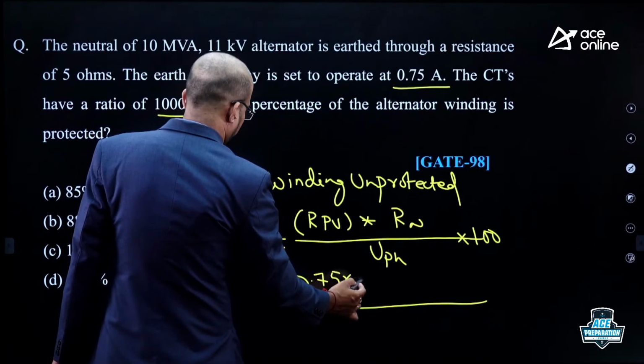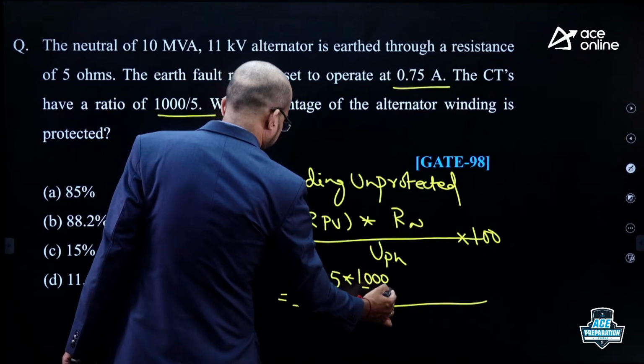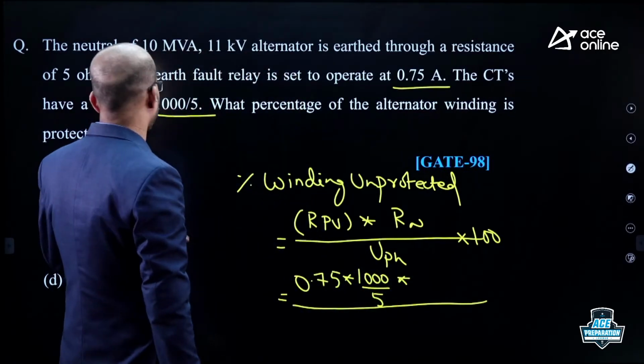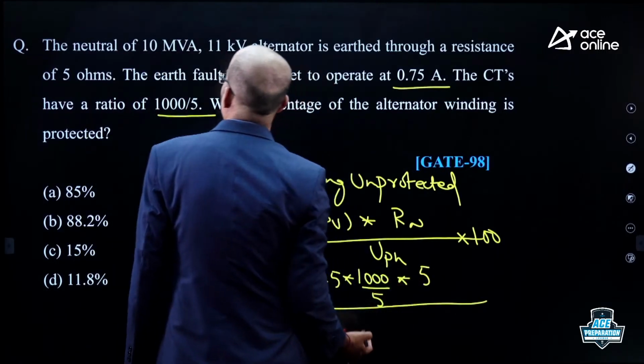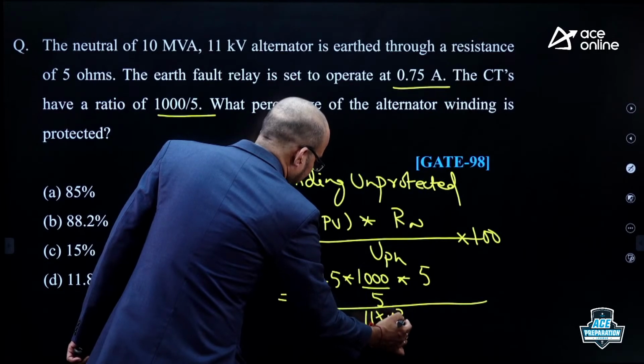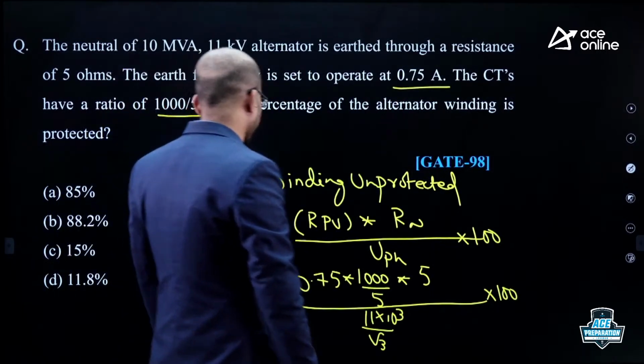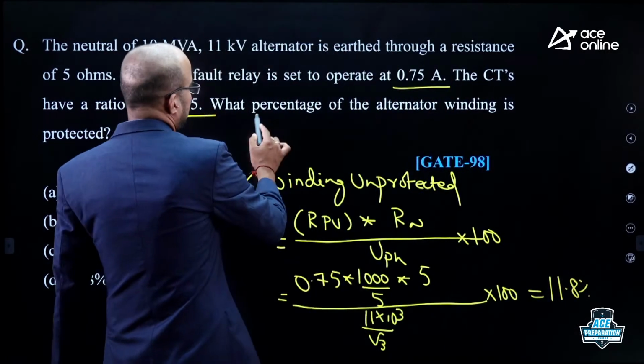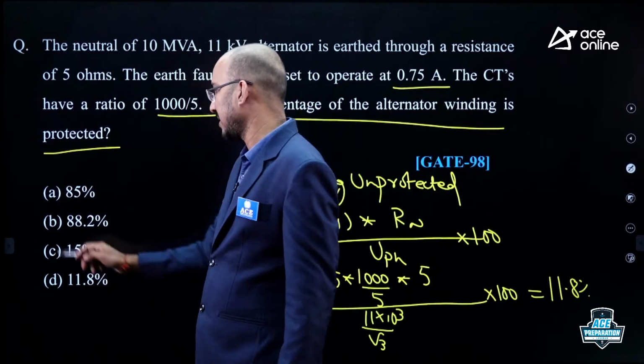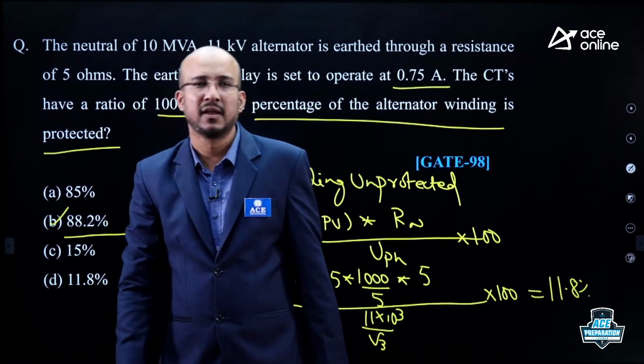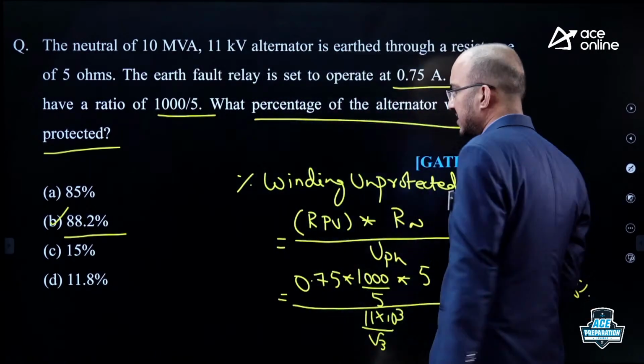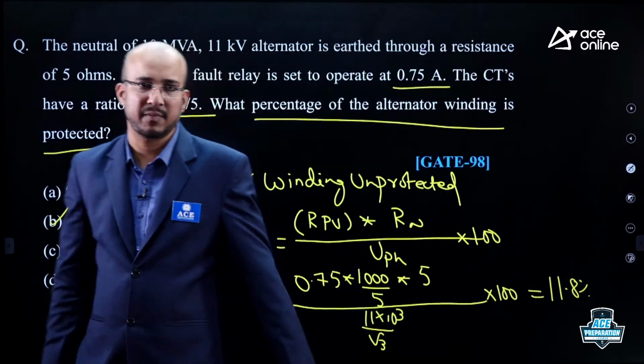So, how do you transfer that? That is 0.75 given into 1000 by 5. Neutral resistance grounded is given as 5 ohms. Voltage is 11 kV, that is line voltage, so phase voltage is 11 into 10 power 3 by root 3, multiplied by 100. This gives the percentage winding unprotected as 11.8%. This is unprotected, but he is asking for the percentage winding that is protected. So, 88.2% is protected. Some short relations are to be kept in mind while solving this type of problems.